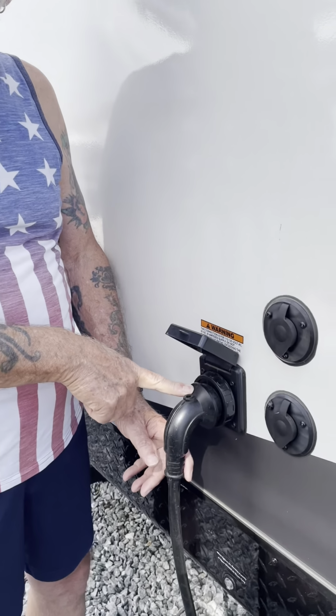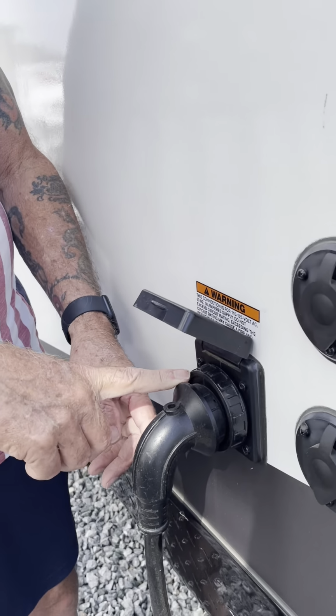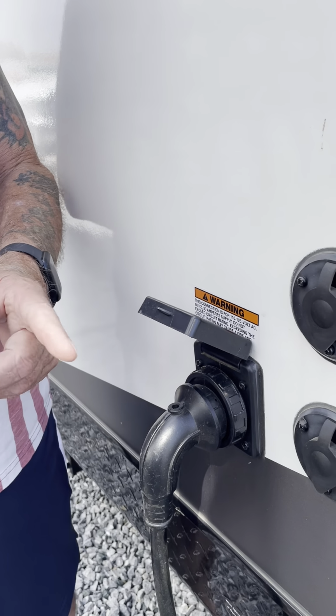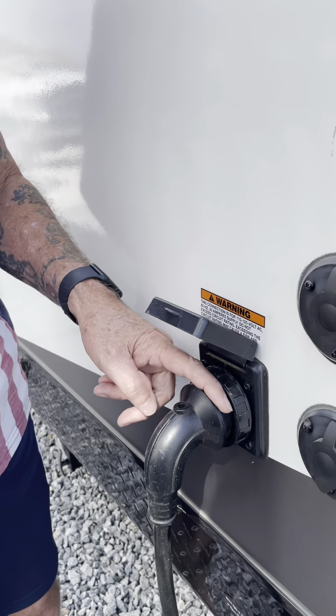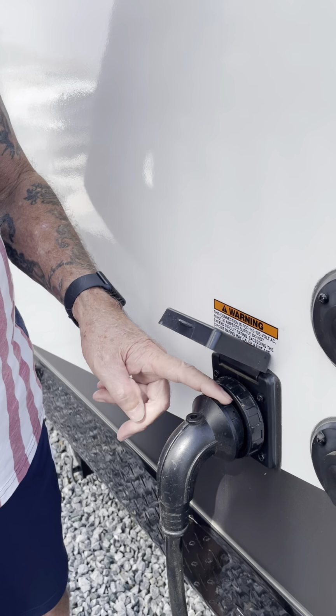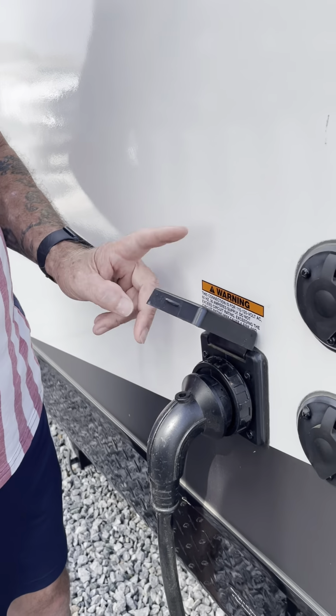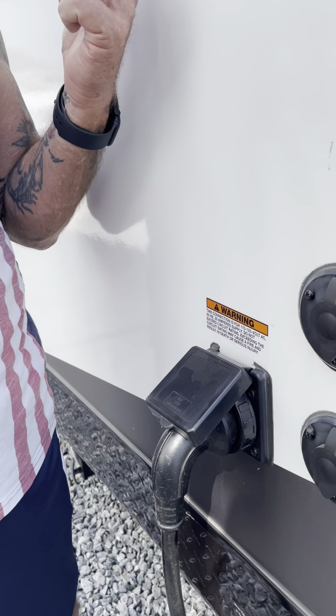It could be a problem with your cord. You can remove the cord and use that same 2-person procedure that you used at the pedestal to verify you have power at the cord. If you have power at the cord, then you're losing power somewhere between this outlet and your circuit breaker panel. It could be wiring. If you have an onboard generator, it could be your automatic transfer switch. If you run your generator and you have power, and you turn your generator off and you still don't have power, then the transfer switch could be stuck or defective.